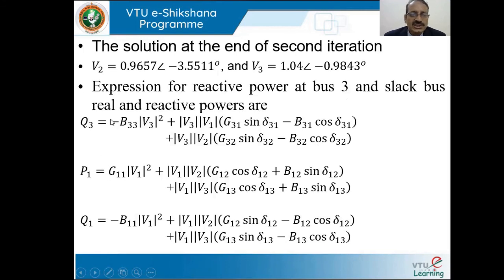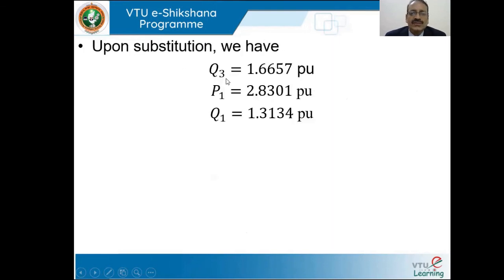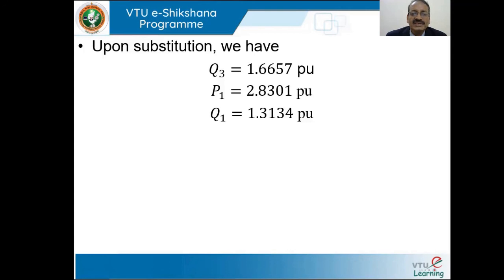Q3 is not computed during the PV bus iterations, so we calculate it now: Q3 = 1.6657 per unit. The slack bus powers are P1 = 2.8301 per unit and Q1 = 1.3134 per unit. The solution is not fully converged here — it will take one or two more iterations. Students are encouraged to continue on a similar basis until convergence is reached, or use a computer program; convergence is typically achieved within 4 to 5 iterations.